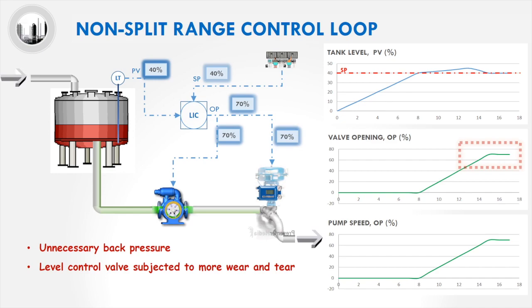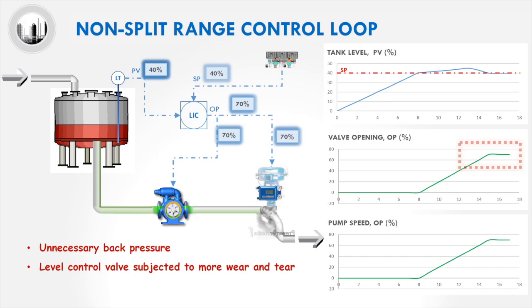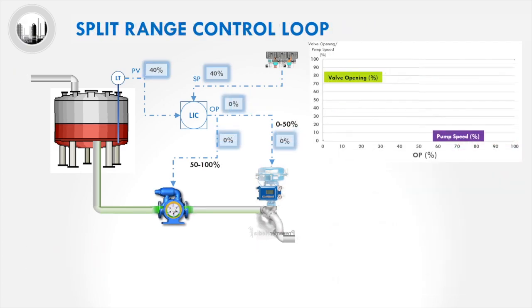The smaller opening of the control valve will also subject the seat and plug of the control valve to more erosion, thus shortening the lifespan of the control valve. We will now evaluate how split range control will overcome these issues.